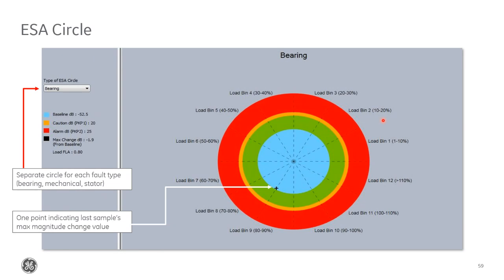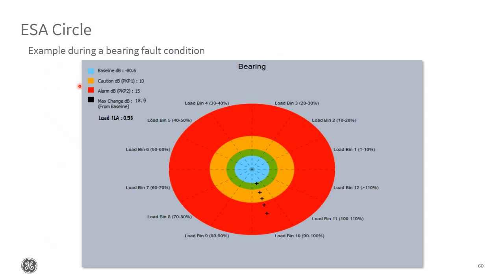Just an example, here's a screenshot I took from a relay in service running the ESA feature. You can see the max change value is right around the baseline radius, so everything looks good here. And then you can see the drop down menu, where you can select which of the three circles you want to look at. And in this example, you can see the points heading outwards indicating a bearing fault. So you can see originally it was at baseline, then it entered the initial fault stage, and then it entered the really bad fault stage. So definitely if you saw something like this, you know you need to take a look at it.